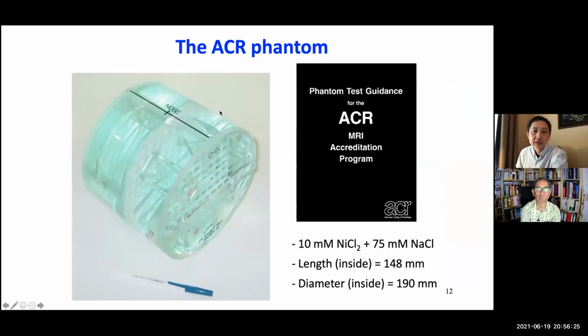So the ACR phantom is a very important one. So I want to describe it a little bit more. This is what the ACR phantom looks like. You place this typically in a head coil. This is a chin, this is a nose. And the phantom size is 148 millimeters in length and 190 millimeters in diameter.